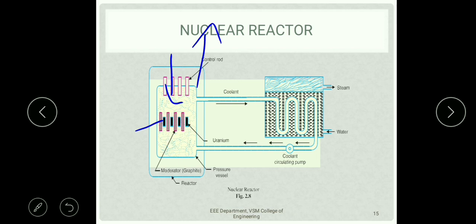So that is the control rods of cadmium, which are inserted into the reactor. Cadmium is a strong neutron absorber, and regulates the supply of neutrons for fission. When the control rods are pushed in deep enough, they absorb most of the fission neutrons, and because few are available for the chain reaction, it therefore stops. However, as they are withdrawn, more and more neutrons cause fission, and thereby the intensity of the heat produced increases.